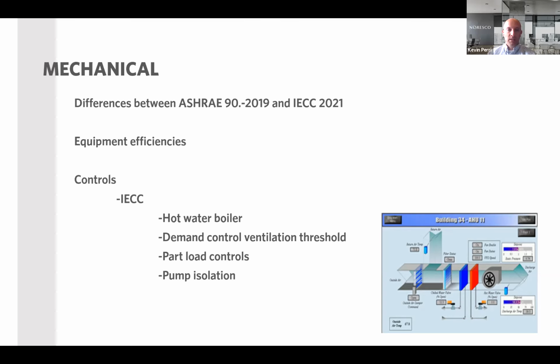So IECC has the most differences in controls, and those are your hot water boiler. IECC has an outdoor temperature setback, or a reset based on your outdoor air temperature for your boiler. Demand control ventilation threshold is different in IECC than ASHRAE. IECC is based on the average occupant load of 15 people or greater per 1,000 square foot of floor area. That's what your demand control ventilation is on. But ASHRAE says that it's 25 people or greater. So the difference is how many people are in that space: 15 people or greater for IECC, or 25 people or greater for ASHRAE, for when demand control ventilation is needed.